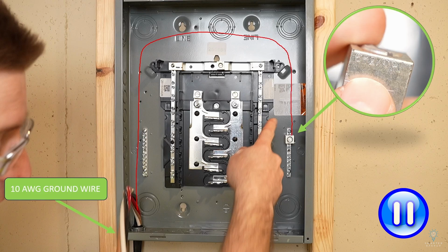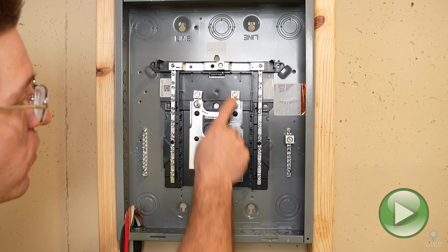into that lug. And you absolutely could have installed this bus bar over here upside down, so that lug was right here. Then you could simply take your ground wire and install it directly into that lug. That would have been totally acceptable as well. That's the thing with these ground bars, is they're really not fussy. Install them where they fit, where they're approved to fit, and land the wire in whatever lug they are rated for. We have to leave the neutral and the ground separate in this panel.